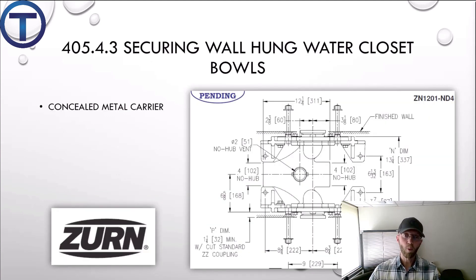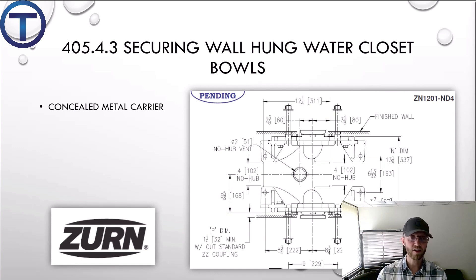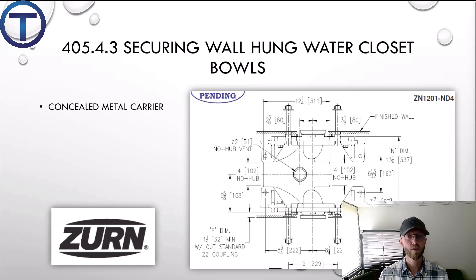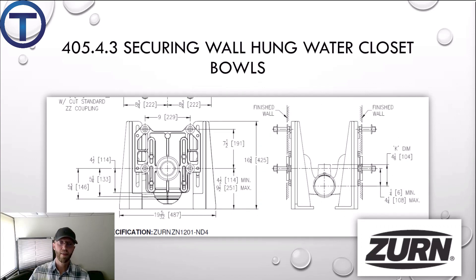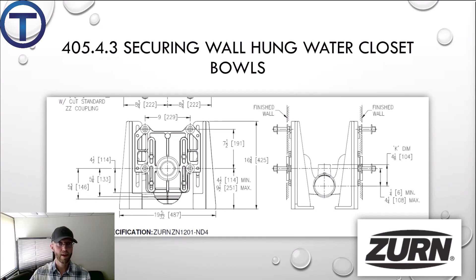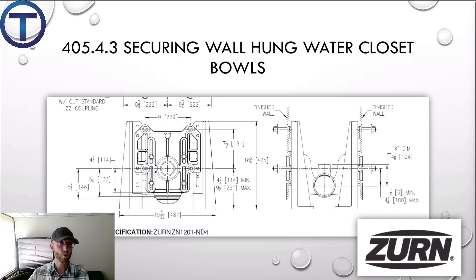For wall-hung fixtures, they have to be concealed inside the wall in a chase — a space where these big cast-iron units are built. They have bolts that protrude through the wall, plus a barrel or pipe that connects to the toilet and conveys the waste. Zurn is one manufacturer of these; they have big cast-iron carriers with face plates and adjustable bolts so you can get the right height. When it's time to set the fixture, by setting these bolts correctly you can get your toilet elevation right for a regular height or ADA height.